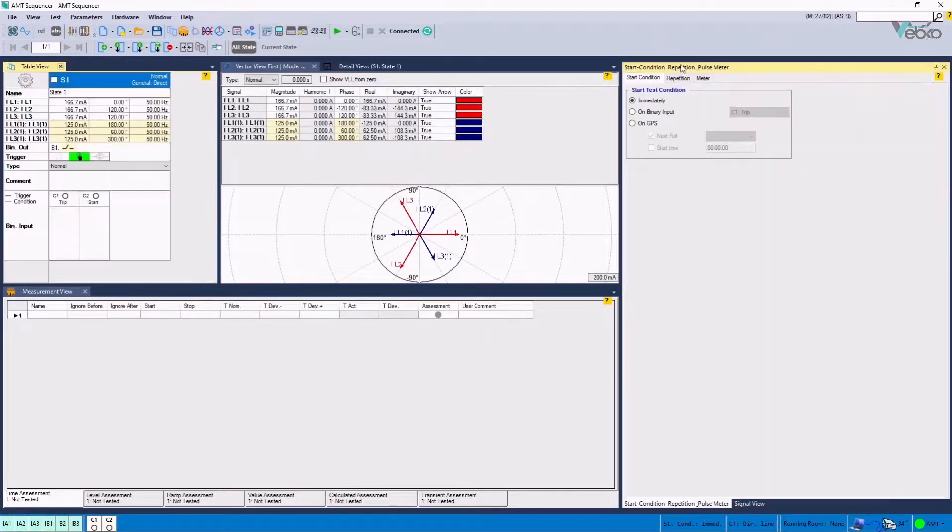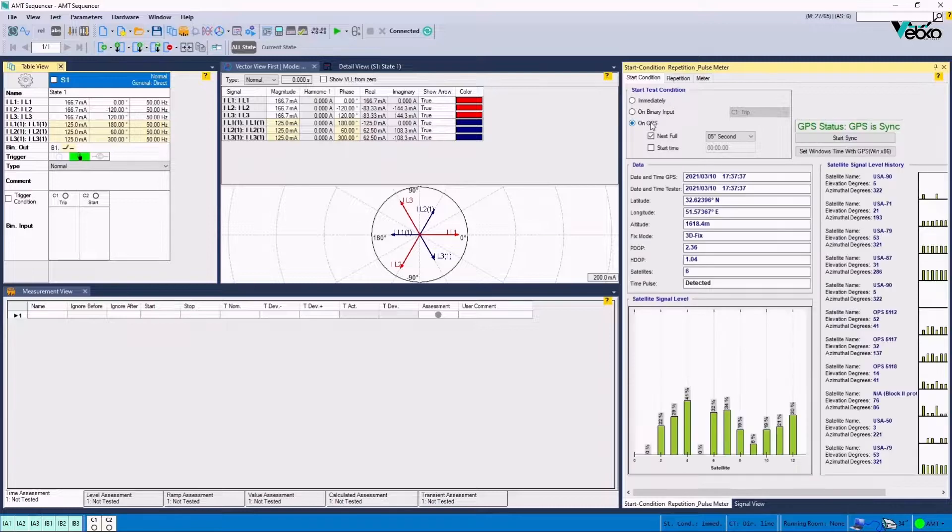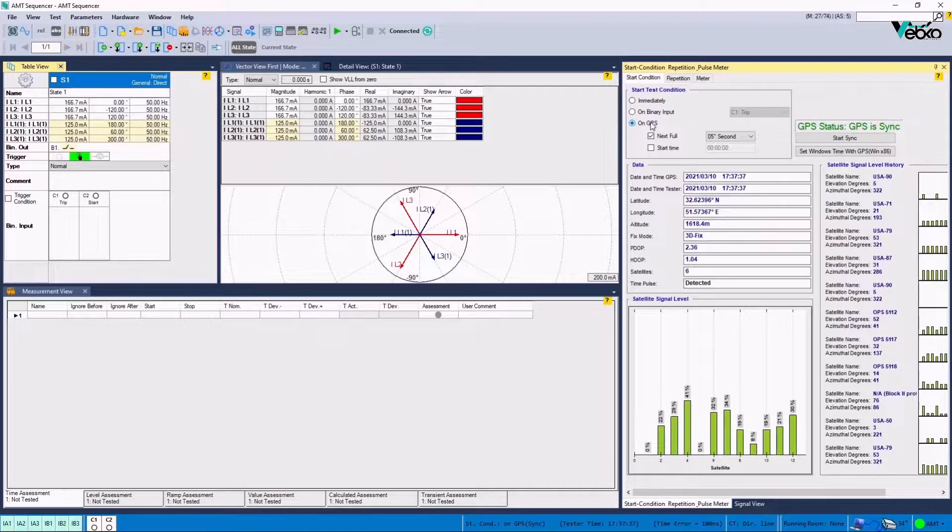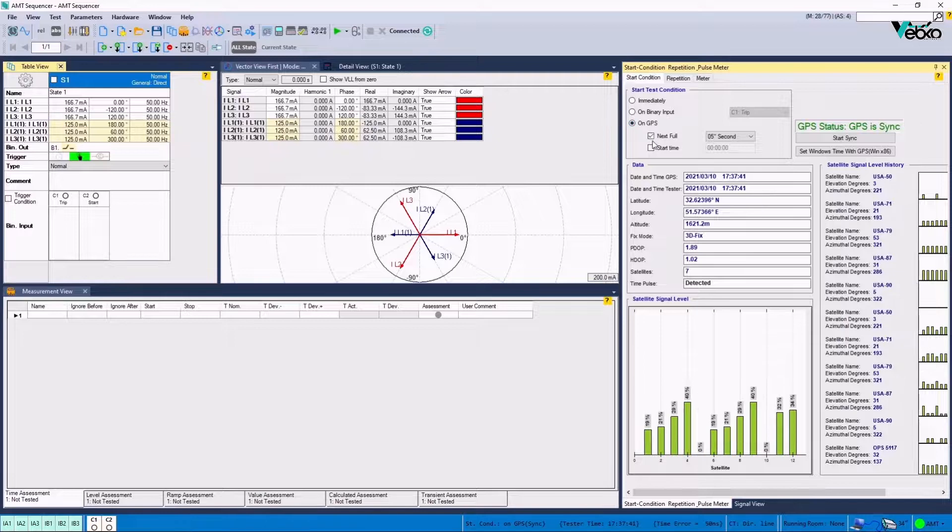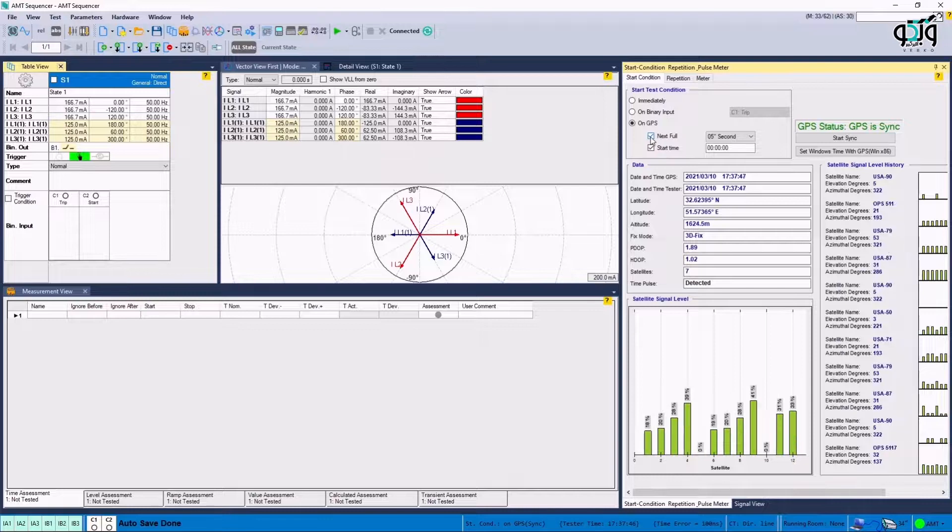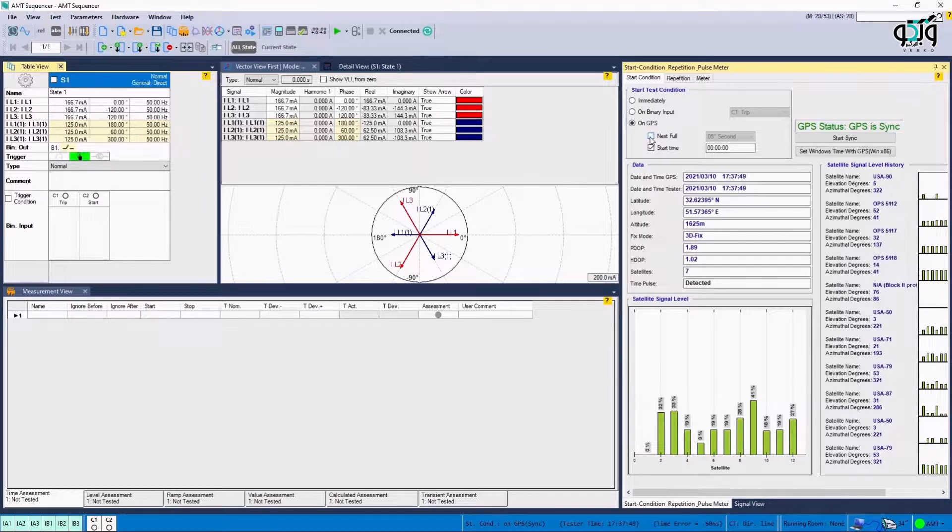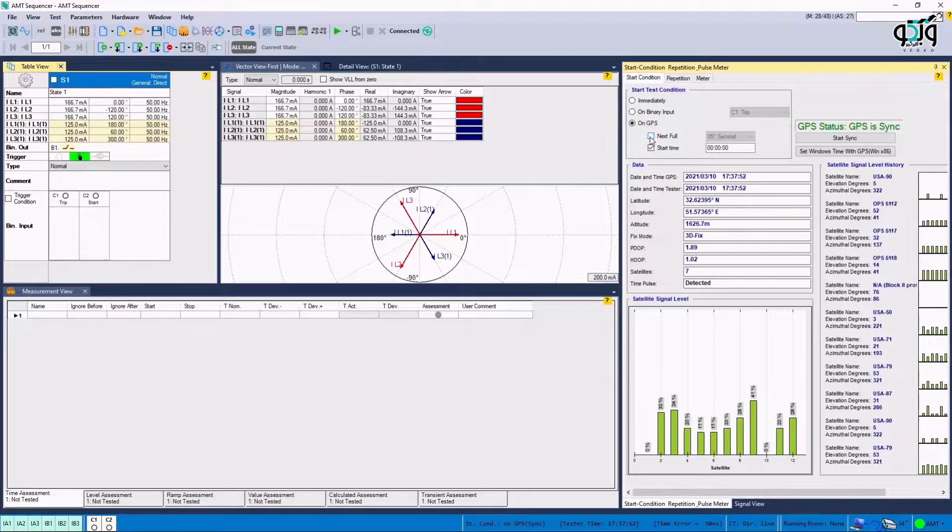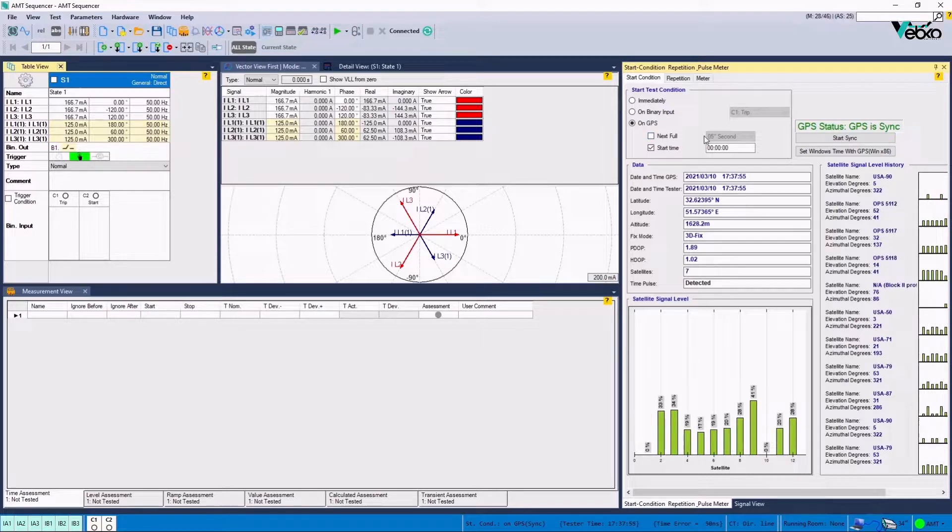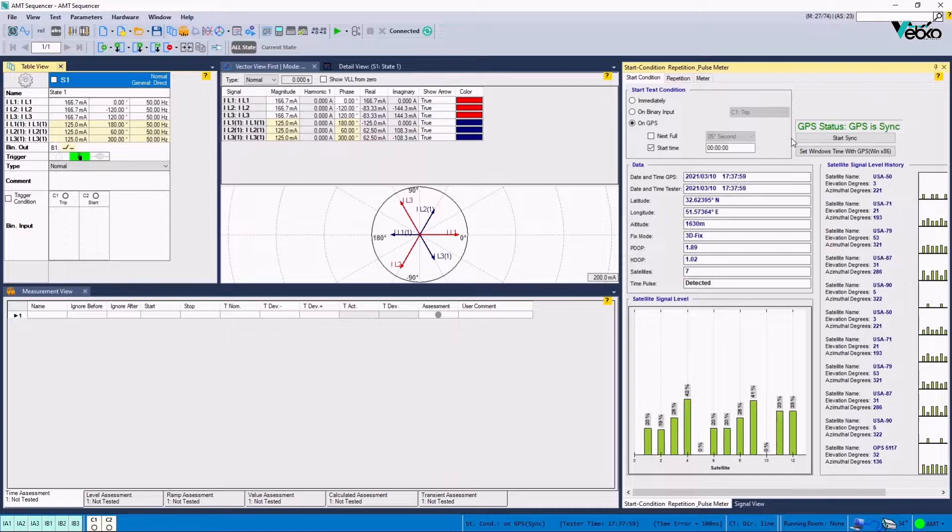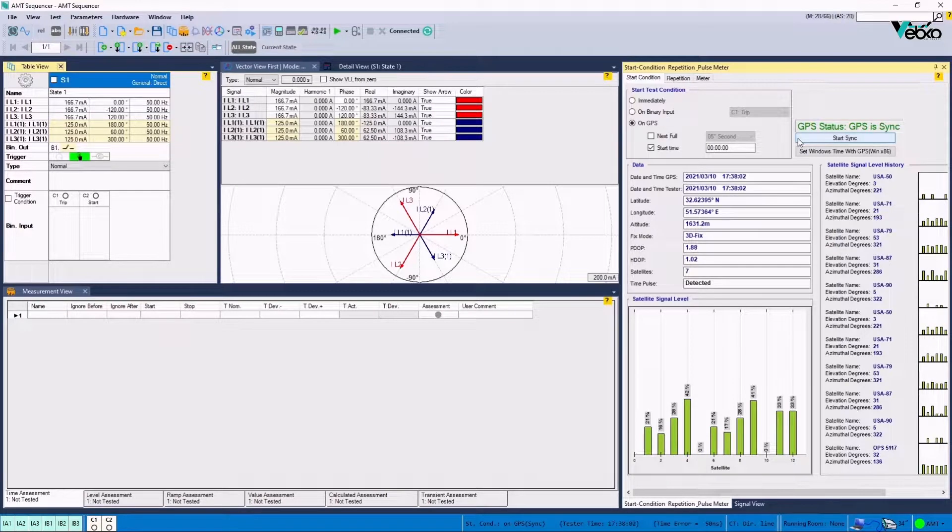In the Start Test Condition section, the third option is related to the coordination of GPS for initiating the test. Start Time and Next Full options are related to the start time of the test and the duration of pause before every injection, respectively. If Next Full option is unchecked, the injections will be done repeatedly and without any pause. In this section, a time should be specified as the test start time in coordination with the other side, which is Remote Post.